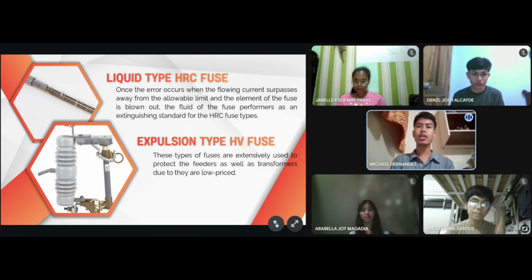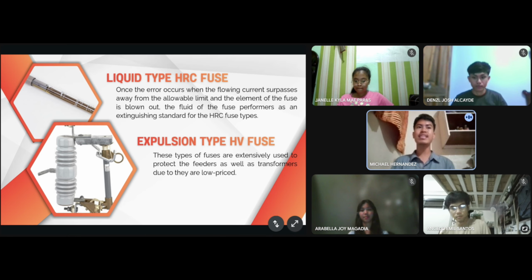So the liquid type HRC fuse is a protective device designed to handle very high fault currents safely and efficiently. Unlike ordinary fuses, this type uses a special liquid, often an insulating oil or other arc-quenching fluid, inside its body to help extinguish the intense electric arc that forms when the fuse operates.